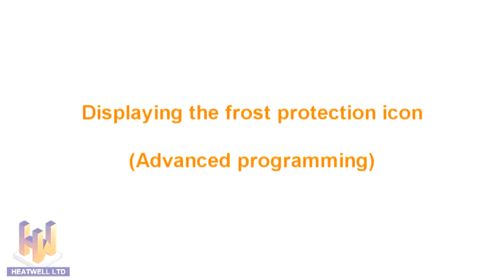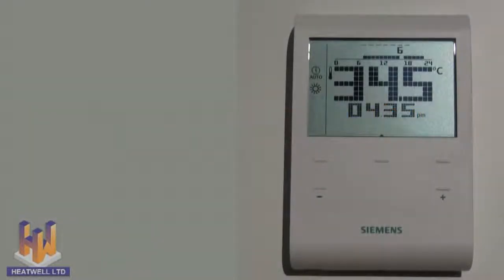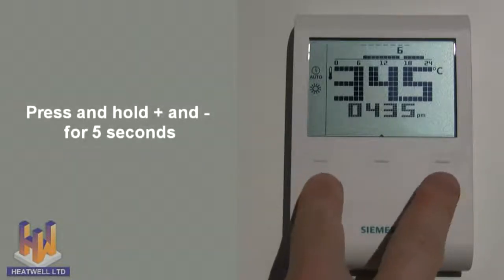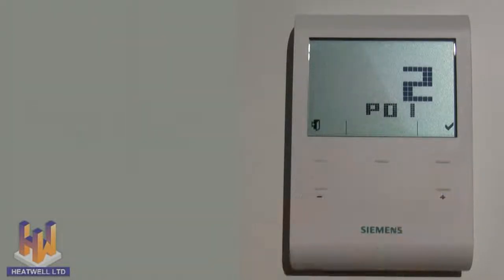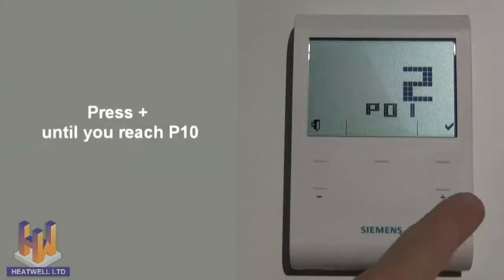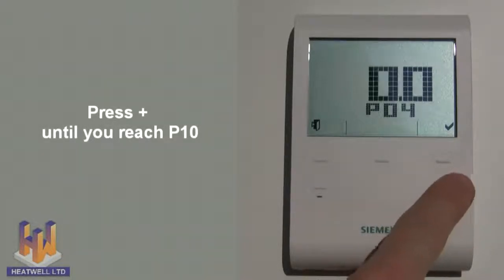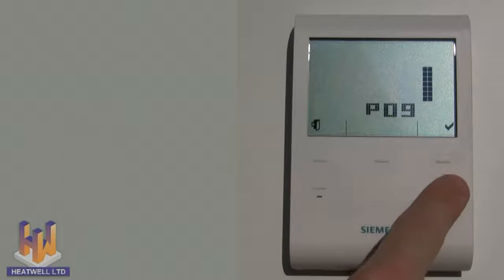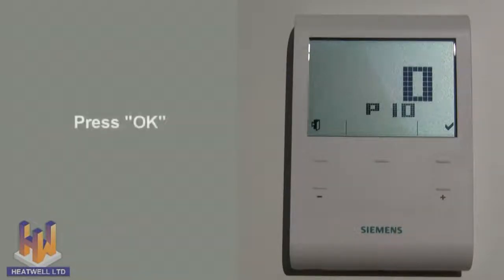Displaying the frost protection icon. To show the off or frost protection icon, go to the Advanced Settings menu by pressing the plus and minus buttons for 5 seconds, then let go. P01 will show. Use the plus button until you see P10. And then press the OK button.